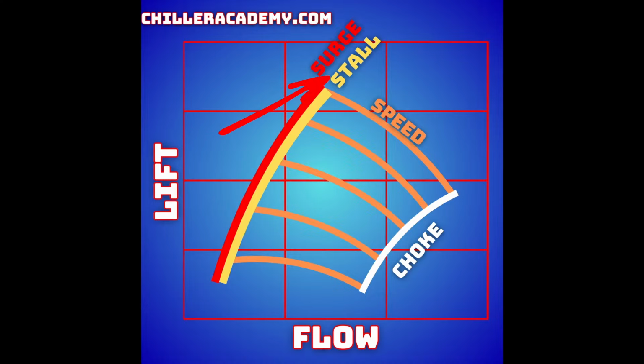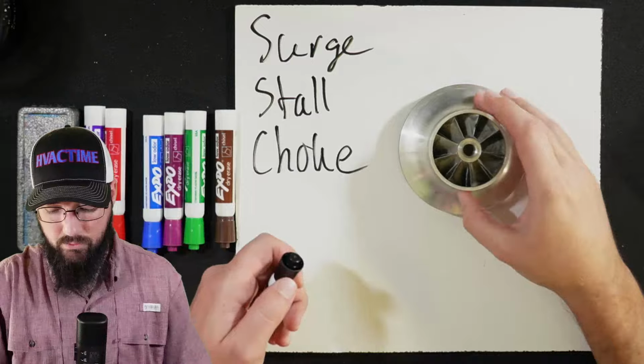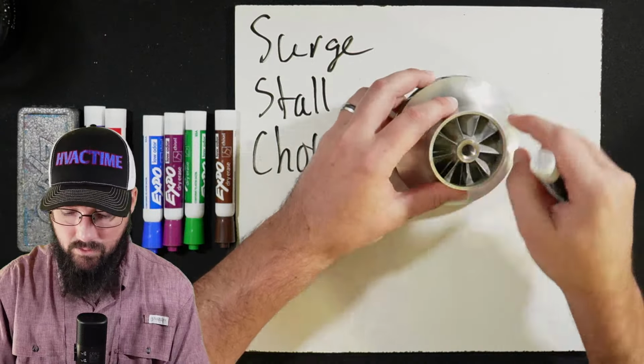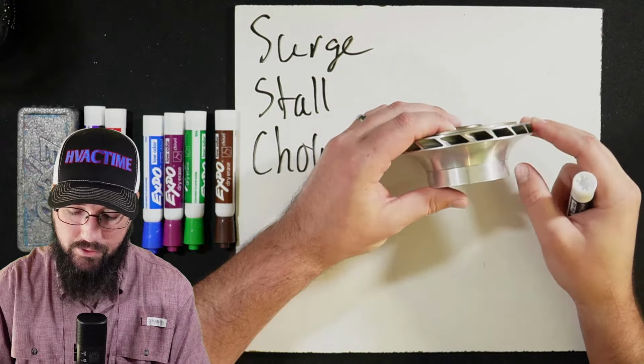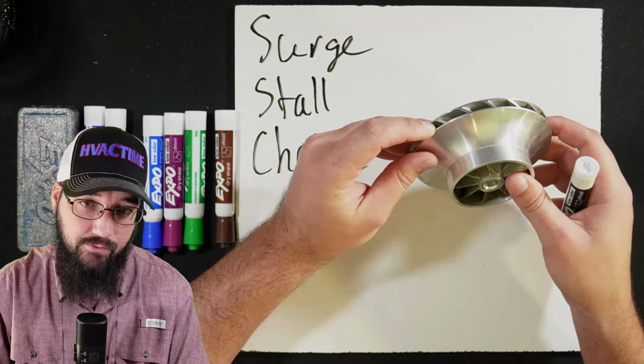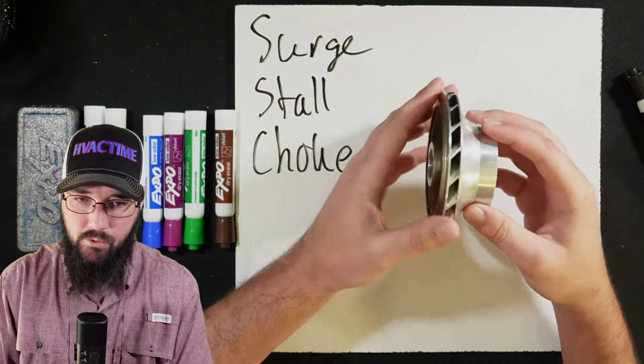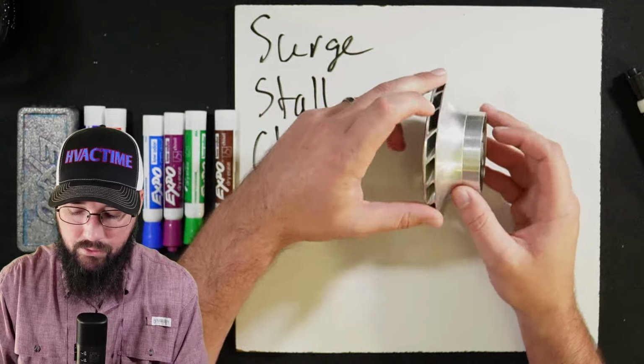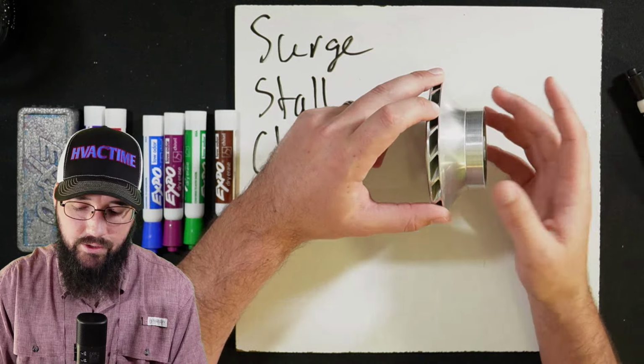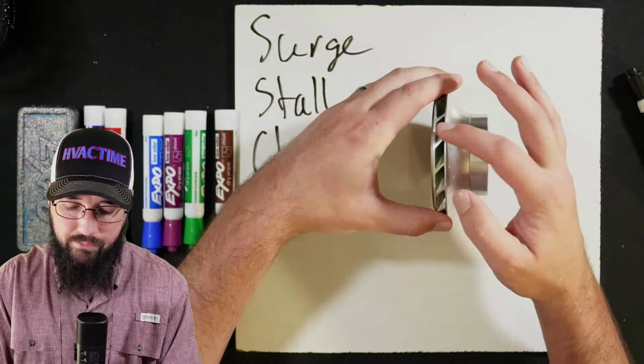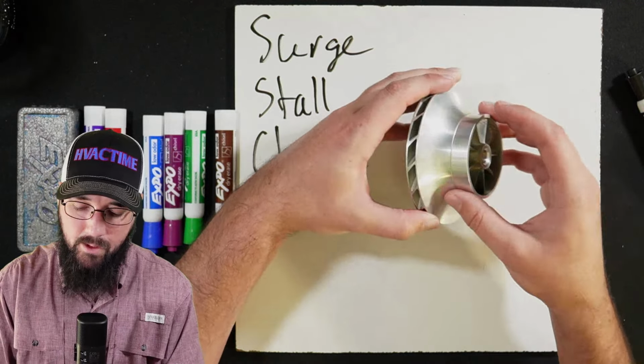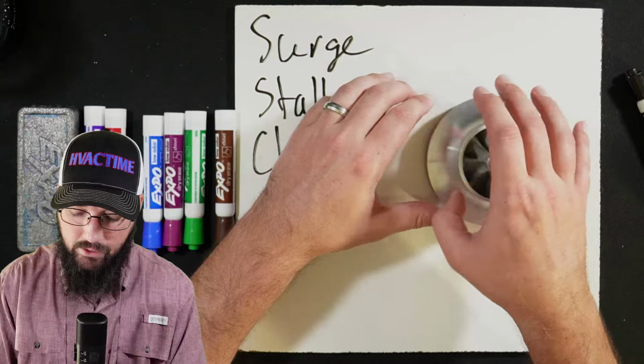Stall is what's happening just before we actually enter into a surge, okay? And I'll actually pull my example down here. So looking at an impeller, this is our suction eye, this is our discharge side going into the diffuser. So as this is running, we get too high of a lift given the conditions, and we backflow. That's our surge.